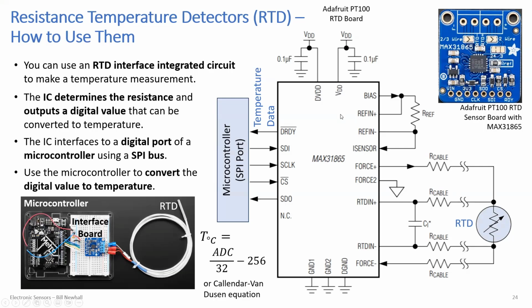If you look on the right, here's the RTD, using a 4-wire approach. There's force plus and force minus with arrows here, so current flows out of force plus, through the RTD, and to force minus. Then RTD in plus and RTD in minus are the voltage measurement.